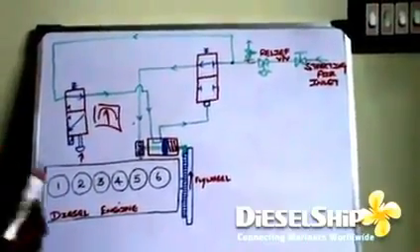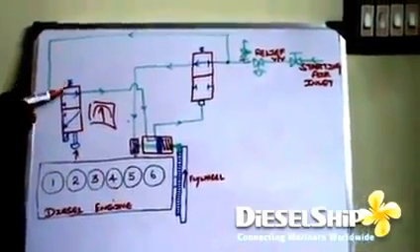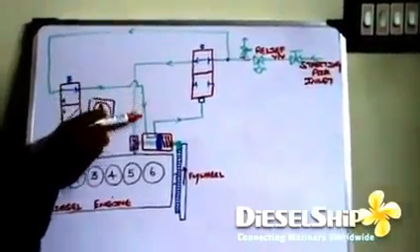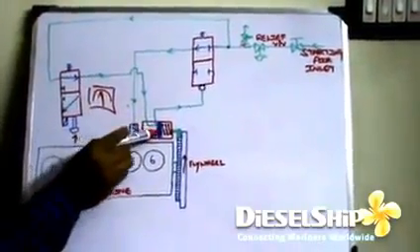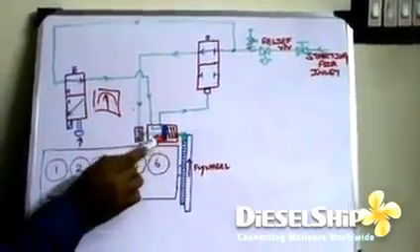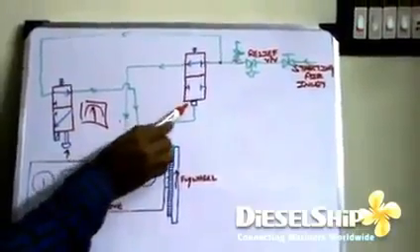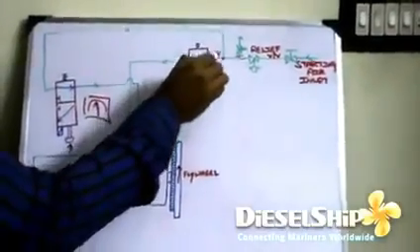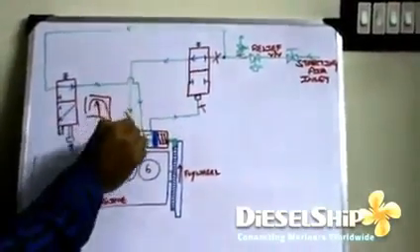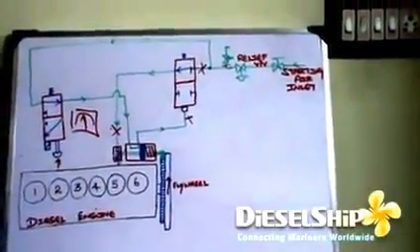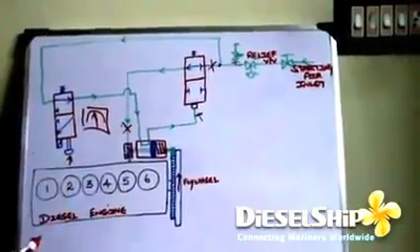So once I release it, immediately due to the spring force the valve shifts and the line gets vented. This line, the air behind the piston gets vented, which means the piston due to the spring force will come back to its original position, thus the pinion is disengaged. And this control valve, since there is no air supply, shifts back stopping the air, and no more air supply for the vanes. So the air motor stops working at this time. Thus the engine is started and then it picks up on fuel.